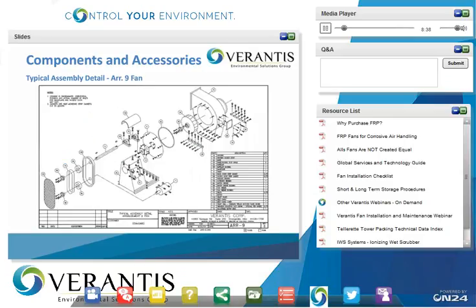This is a view for arrangement 9. Most of the components are going to be very similar to arrangement 10, but there are a couple of differences, with one being the motor mounted on the side of the base, adjusted by a separate piece of adjustable motor base. Also, with the guards, there is a separate piece of shaft guard as well as belt guard. With the belt guard, we will have stainless 304 stainless steel expanded metal mounted on the face, which is going to help to inspect and maintain the drive as well as help the ventilation.